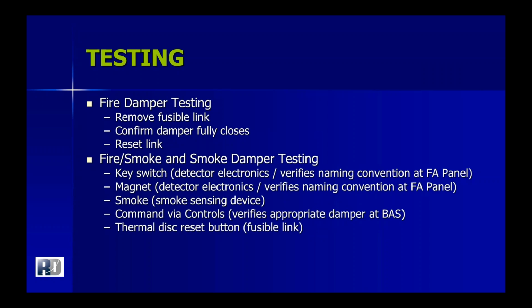This is something that a facility does need to do every 4 or 6 years, depending on the type of building that you're in. For fire smoke and smoke damper testing, there are multiple ways to accomplish this, and it all depends on your end goal. For example, key switches and magnets really test the detector electronics, and while you are able to verify that the damper does fully open and fully close and verify your naming conventions that come back to the fire alarm panel, that is pretty much the extent of what those test. They don't really test any sensors in the device itself.